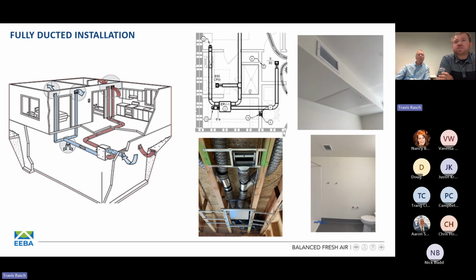The final is a fully ducted install. Just like the name states, we've got dedicated ductwork running on both the supply side as well as the exhaust side. Same principle as talked about before: stale air is extracted from those mainly polluted areas of our home, being our bathrooms and kitchen areas. Certainly you could run it to other areas as well. And then your fresh air is distributed to the main living areas, so the bedrooms, the living rooms, etc. Again, we're leveraging dedicated ductwork to truly get that air exactly where you want it to go and not relying on the ductwork you may have from your forced air system.